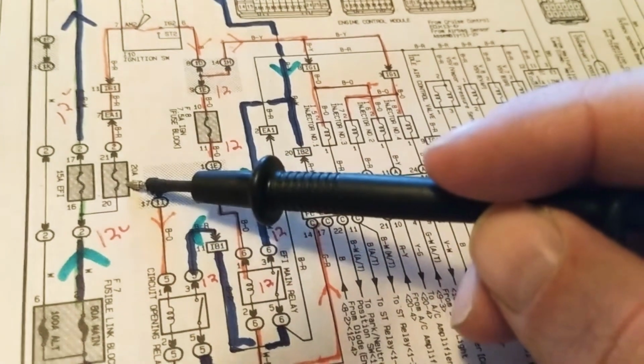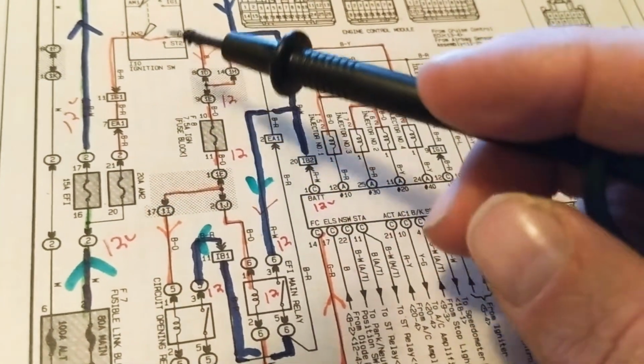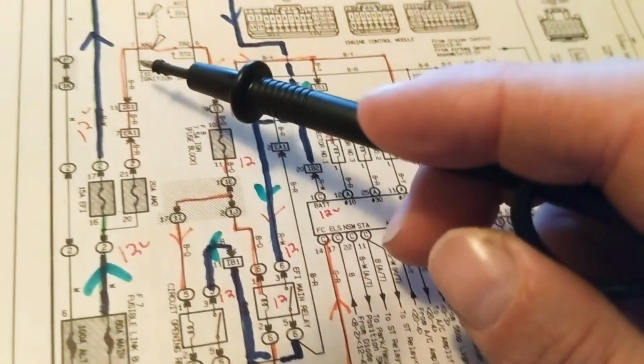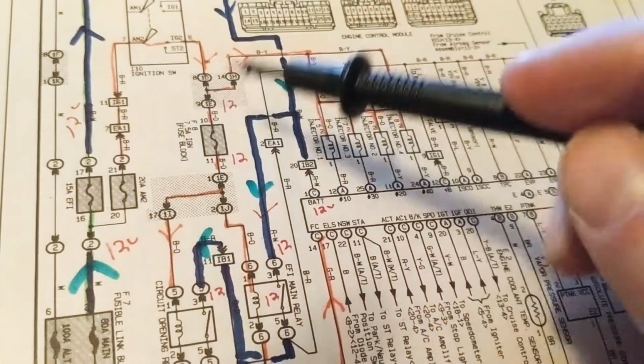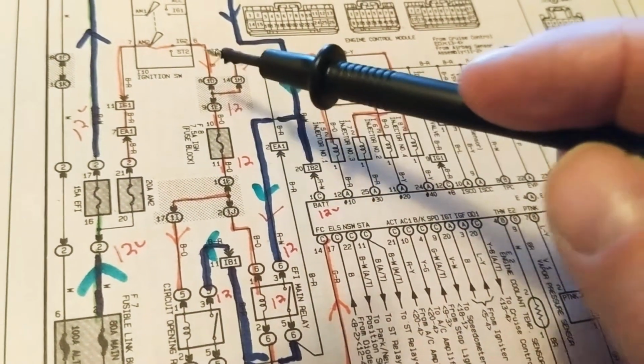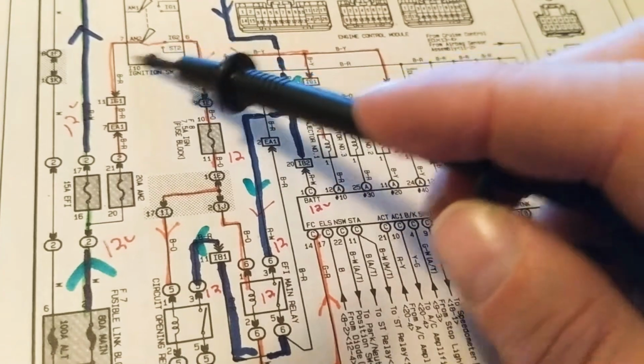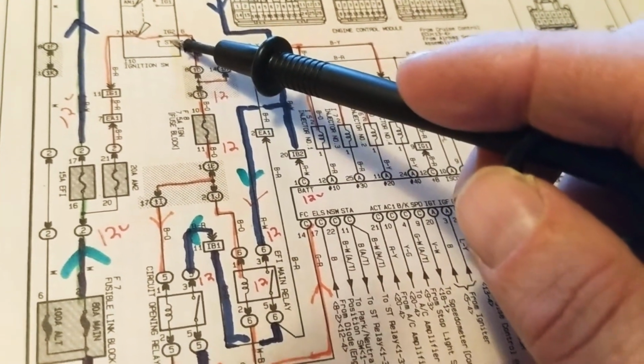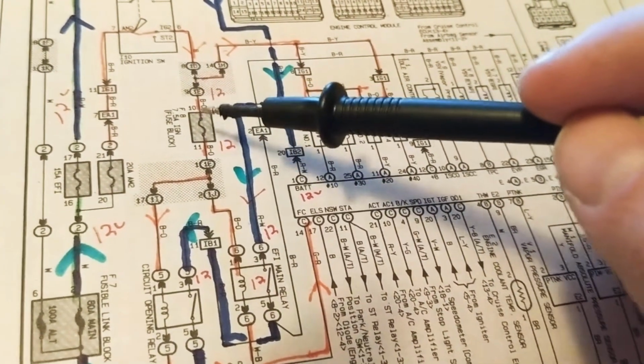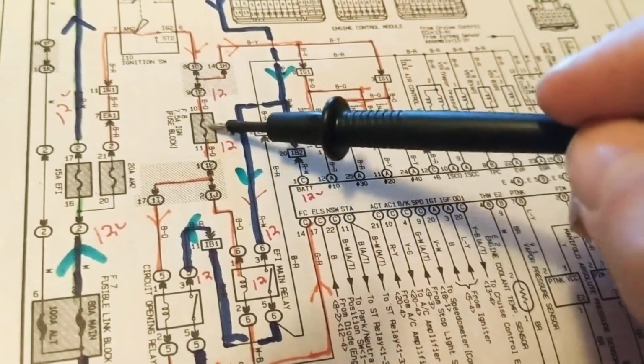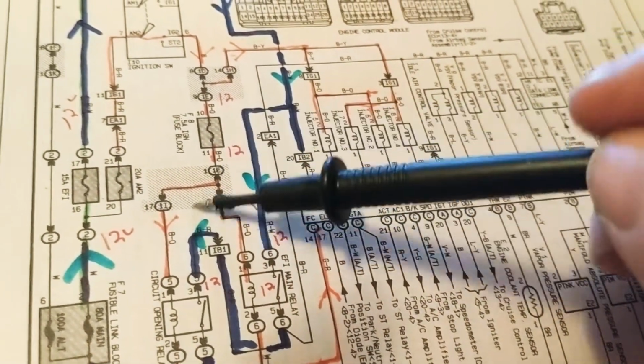It's possible that this fuse opened up, or that there's something wrong here. If I measure 12 volts here and 0 volts over there, that means there's an open in between, or this connection isn't making contact. Or it could be a short from here to ground. If there were a short to ground, the fuse would blow right away.